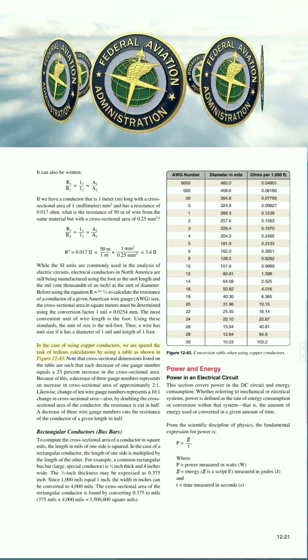In the case of using copper conductors, we are spared the task of tedious calculations by using a table as shown in figure 12-43. Note that cross-sectional dimensions listed on the table are such that each decrease of one gauge number equals a 25% increase in the cross-sectional area. Because of this, a decrease of 3 gauge numbers represents an increase in cross-sectional area of approximately 2 to 1. Likewise, a change of 10 wire gauge numbers represents a 10 to 1 change in cross-sectional area. Also, by doubling the cross-sectional area of the conductor, the resistance is cut in half. A decrease of 3 wire gauge numbers cuts the resistance of the conductor of a given length in half.